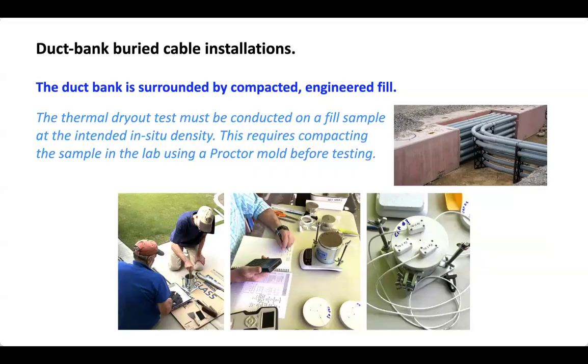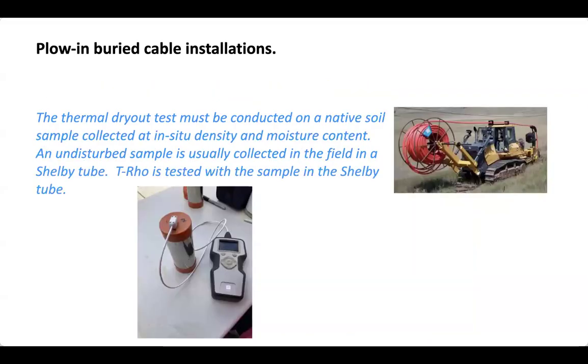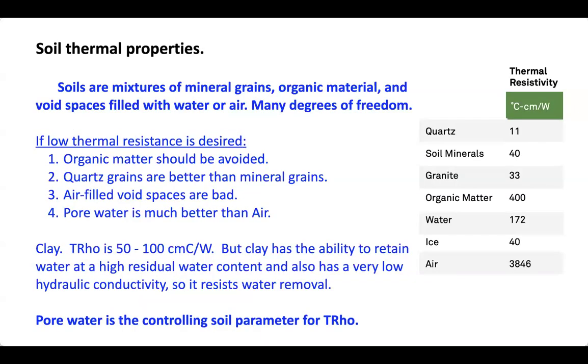So the duct bank is surrounded by a compacted engineered fill. So we have to take the soil, left picture, and put it in a Proctor mold, compact it to the right density, then measure the thermal properties, and then boom, we're done. I write a report. But for plow-in cables, the test must be done on native soil, collected at the proper density and moisture content. And so it's usually collected in a Shelby tube, and it arrives at my company's international headquarters, which is my wife's garage, where I take all these measurements, and we test them like that.